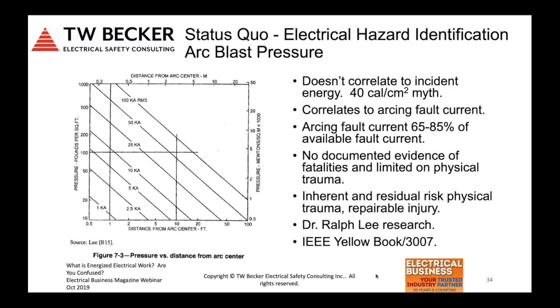So this graph advises you that the distance away from the arcing fault and the fault, that's the arcing fault current in kA shown on the graph, then correlates to the theoretical pressure released from an arc flash in pounds per square foot. All right, so arcing fault current is less than bolted fault current. Again, I emphasize there's no documented evidence of fatalities due to arc blast pressure and limited information on physical trauma, right? So when we do a risk assessment, the inherent and residual risk as far as potential injury or damage to health is most likely and should be considered as a repairable injury due to blast. This is Dr. Ralph Lee's research from the late 1980s. It's also available and documented in the old IEEE Yellow Book or the 3000 series IEEE standards now.